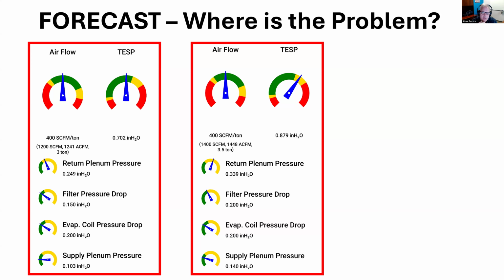So in terms of understanding how this works and what problems we see in the field, I'll give you some information about what we often see. A return plenum pressure that's too high because the returns are undersized is the most common problem for airflow that we see. That means adding a branch to the return. It might mean enlarging a trunk if it's a trunk and branch system. It might be the plenum's too small. So that's the most common problem that we see for airflow.